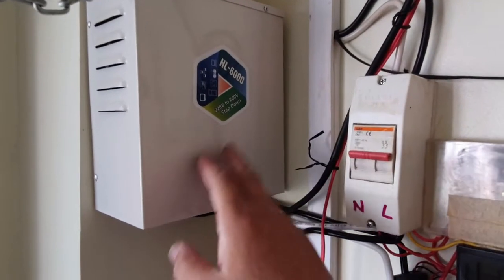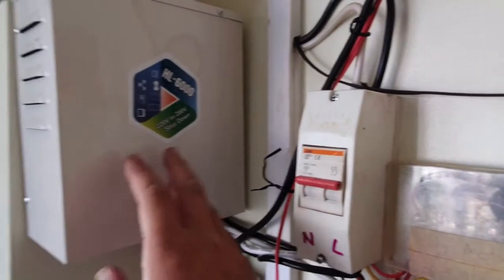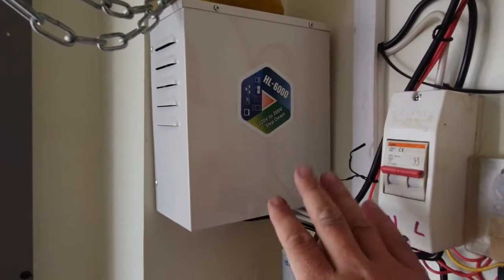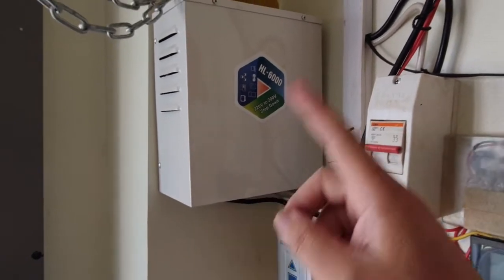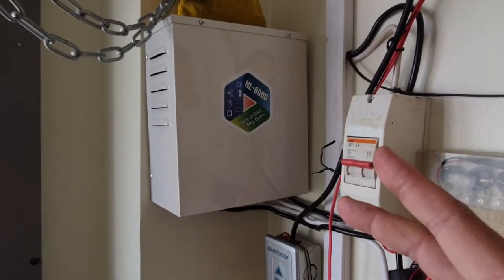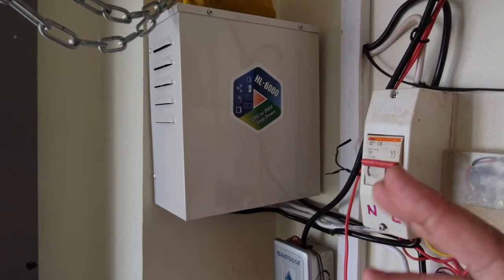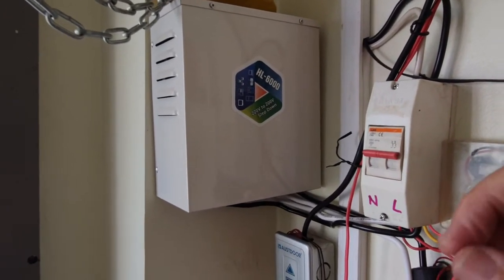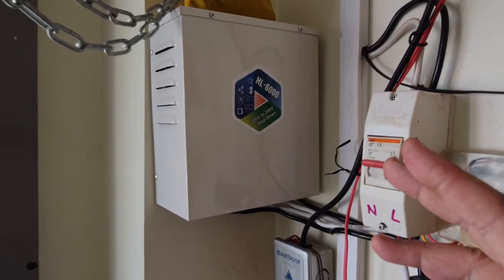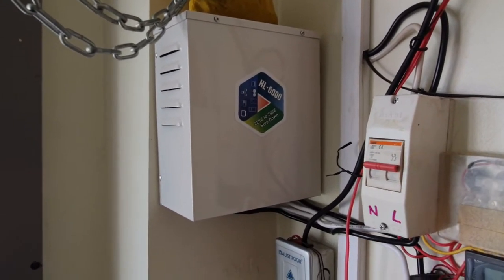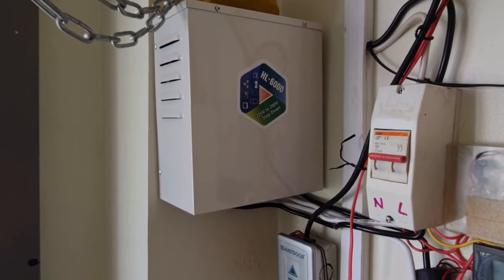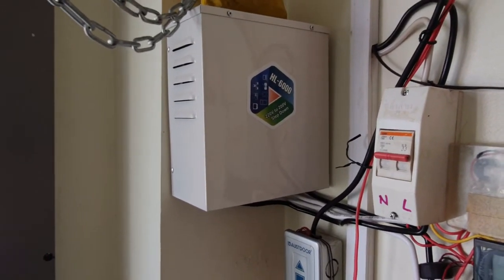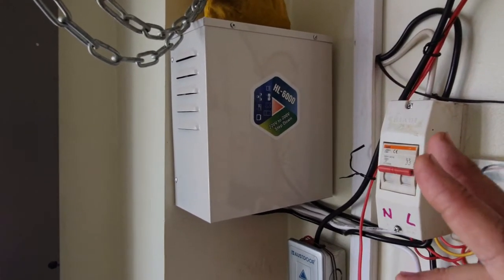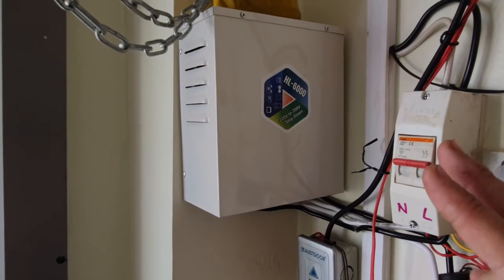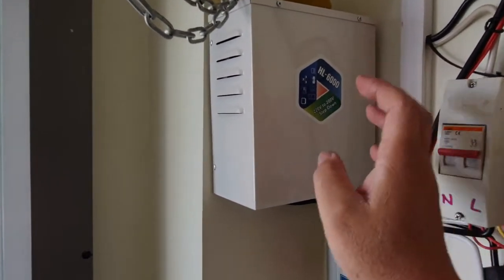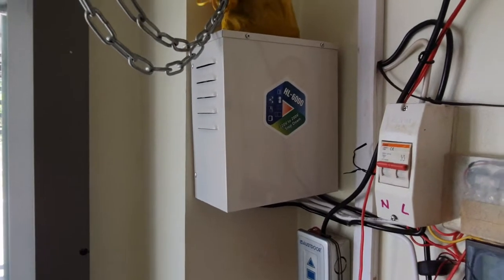So this is actually a step-down autotransformer. It's a static one. Why do I choose a static one instead of the servo type? Because with a servo autotransformer, the reaction time is a few microseconds, or that's the fastest one. But a surge can go much faster than that. That means the surge has already gone through the circuit, and then the autotransformer starts to react. With a static one, there's no reaction time. It's always there, constantly there.